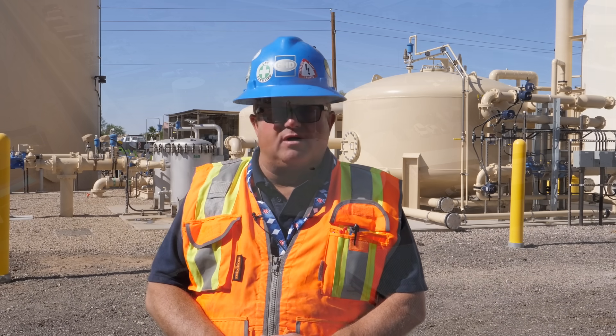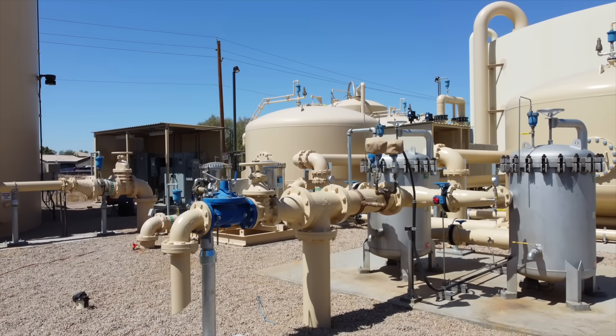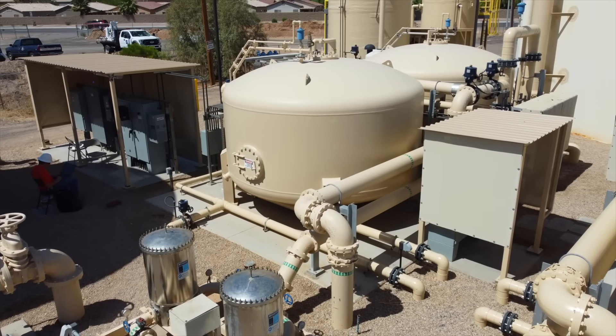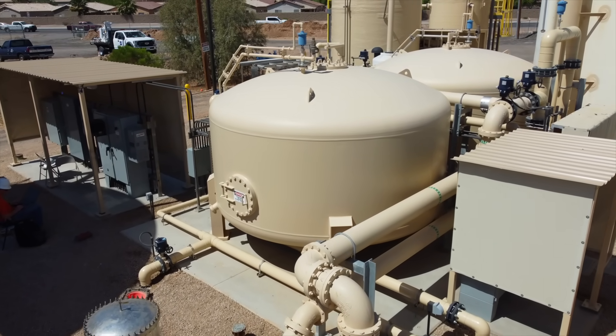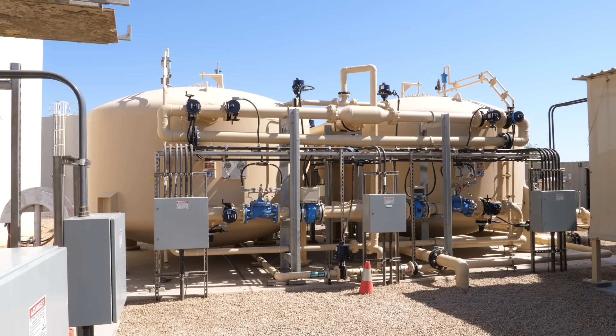This facility was designed and constructed about two years ago. The utility company, which was under management by EPCOR Water, was experiencing extremely high growth in the area, and it was decided that three wells previously placed out of operation for high nitrate levels above the MCL of 10 ppm should be returned to service. Ultimately, the growth rate made it necessary to use those three wells and treat them below the MCL, so this facility was designed, constructed, and is now operating to do that.